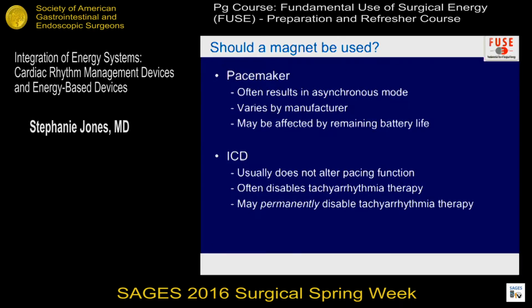If you put a magnet on a pacemaker, you will usually get an asynchronous mode, but it's highly variable by manufacturer. It can also be affected by the remaining battery life. So you may not get the response that you think you're going to get. If you have a defibrillator, the magnet will usually not alter the pacemaker function. It will usually turn off the defibrillator, which is what people are looking to do. But again, if you're pacemaker dependent with a dual device, you may need to actually reprogram it in order to get the result that you want.